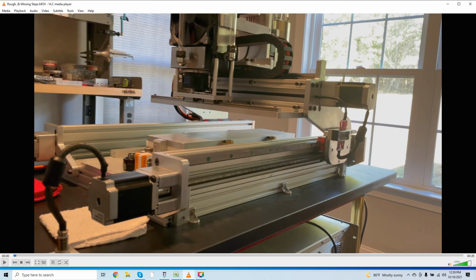Let's check motion. X is clean, meaning smooth. Z is clean and smooth. At that point, we know it's time to continue to move on. We know that we've got everything linear as far as the other 2 remaining axes. However many axes the system has, keep going until it's completed. But overall, what you're looking for is a baseline of consistency.